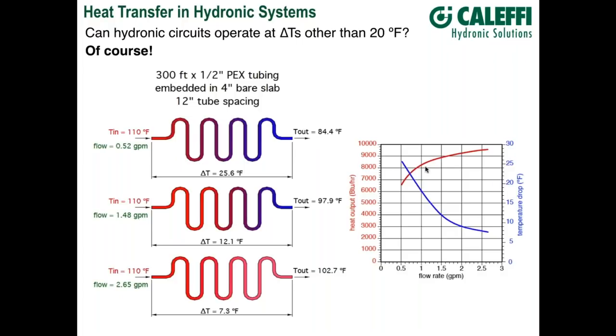The temperature drop of that circuit plotted as a function of flow rate shows a delta T ranging from a little over 25°F down to roughly seven. The rate of heat transfer continues to increase as we increase flow rate, but with a diminishing rate of increase — just like our previous examples. In a hydronic system, higher flow rates produce higher heat outputs in a radiant floor circuit, but the penalty is a significant increase in pumping power.